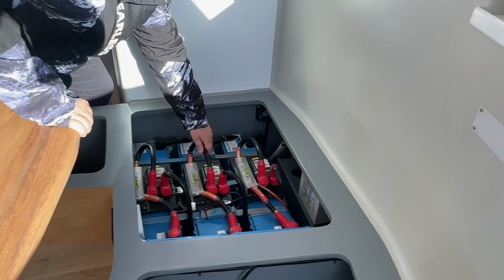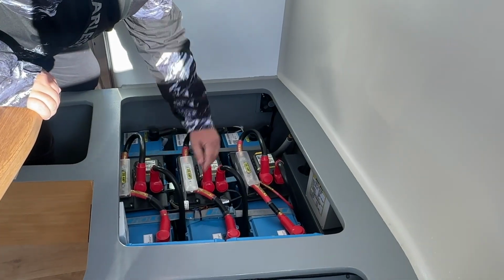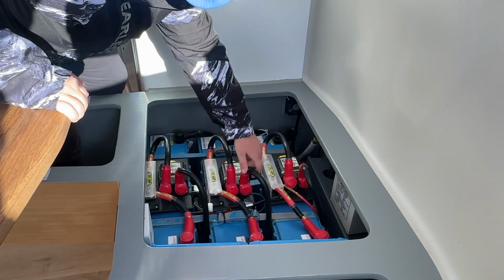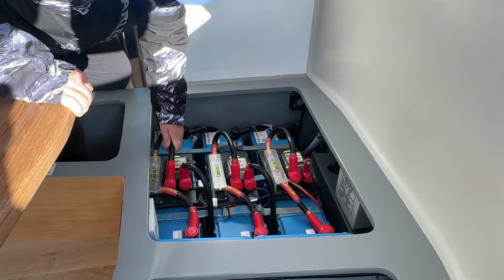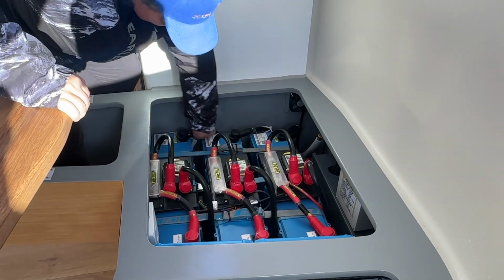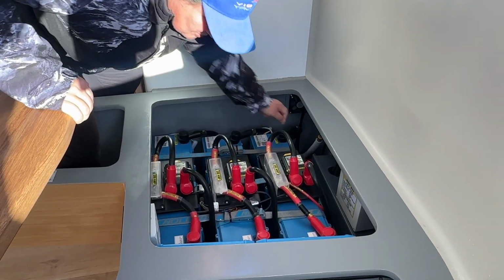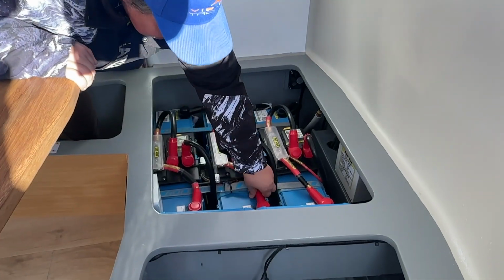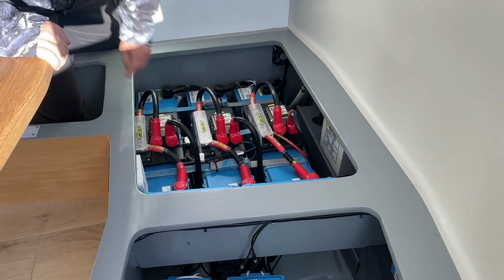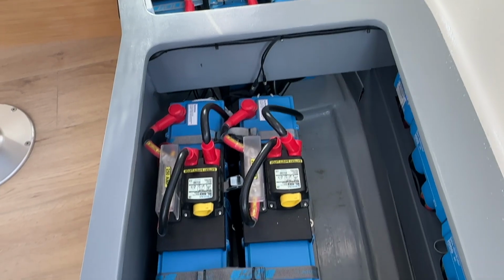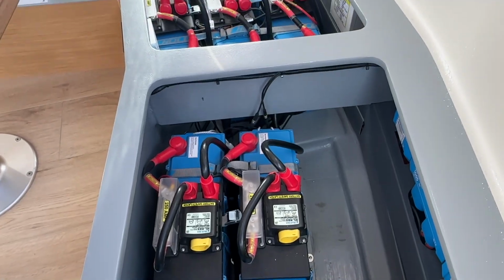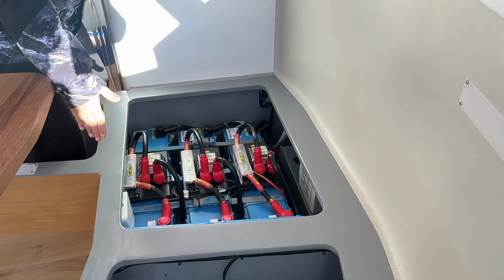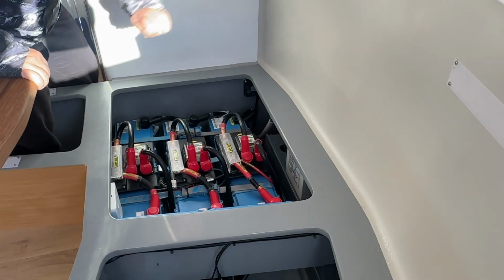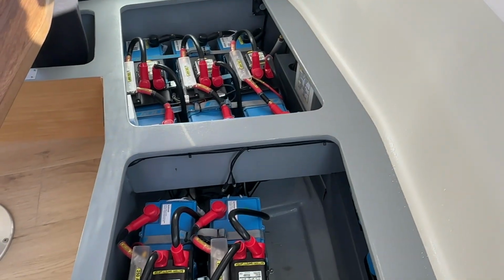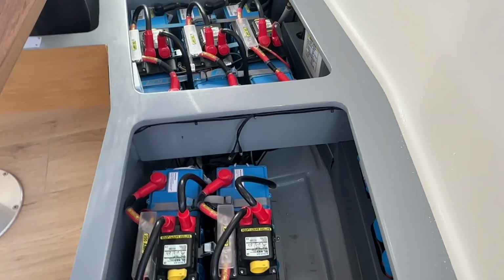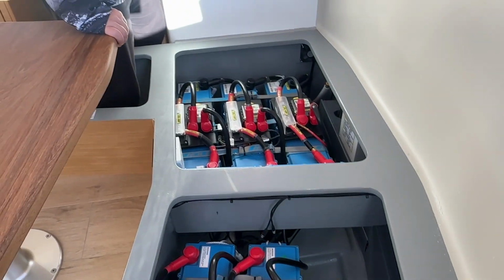We've also got some air coming in over the batteries there, which will also get sucked out. When you have rough seas, make sure your connections are all fast. Do a bit of a shake on them, make sure they don't come loose - you shake the battery, you don't need to use a lot of force. If it's loose, you will immediately see a movement because of the leverage of the cable. So take a visual inspection - you can open up your link distributors, shake them up as well if you feel like that, and check for anything that looks like a hotspot.